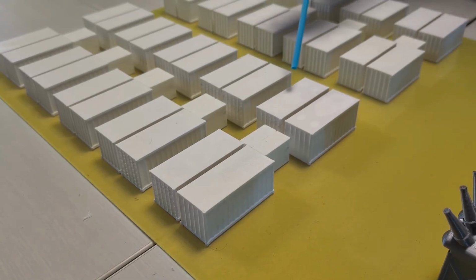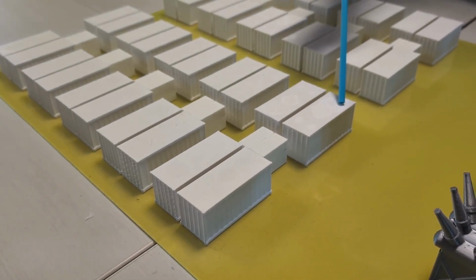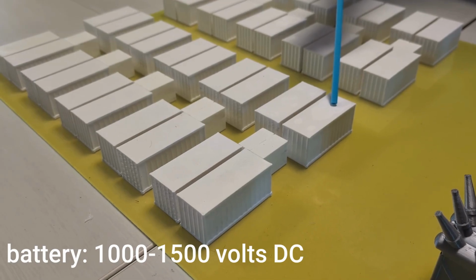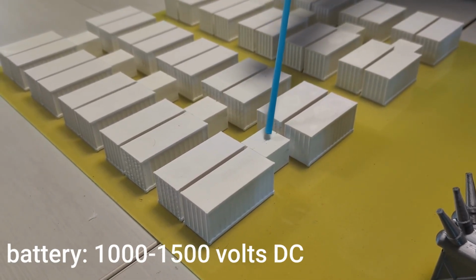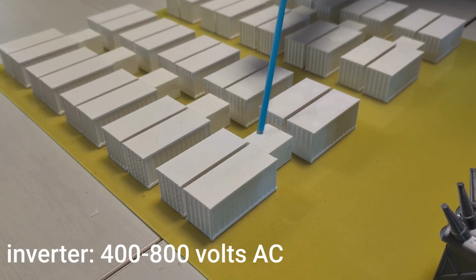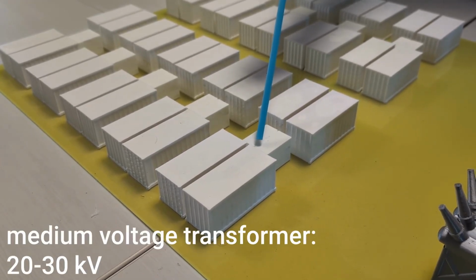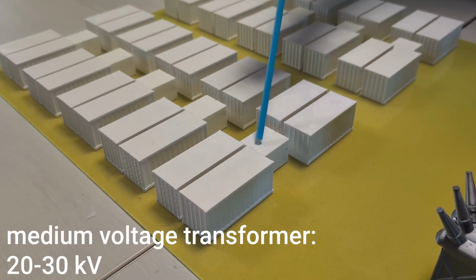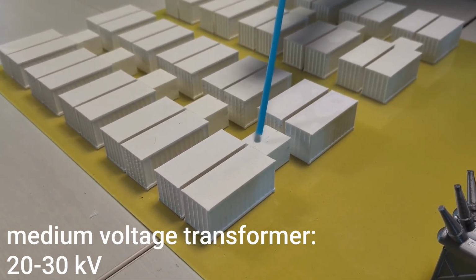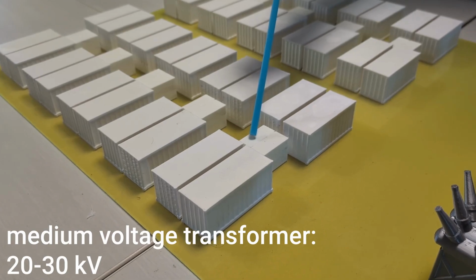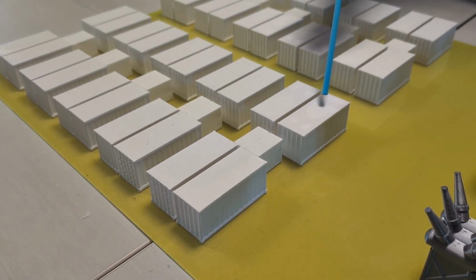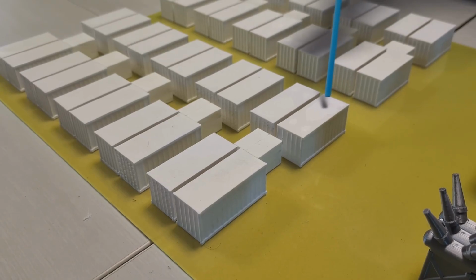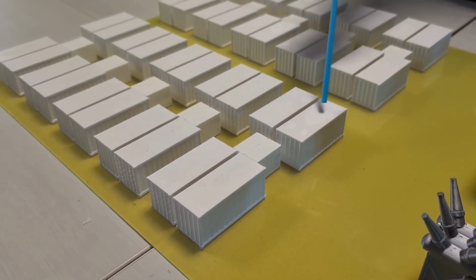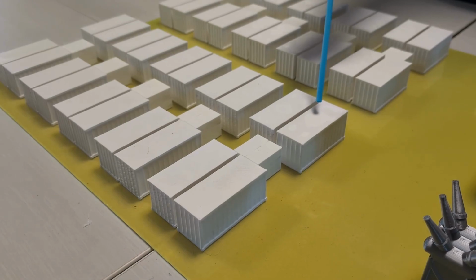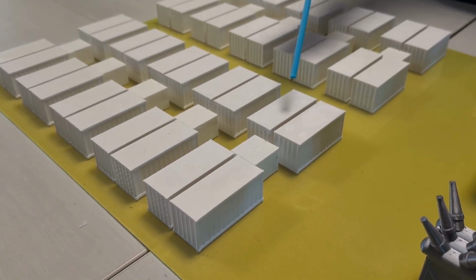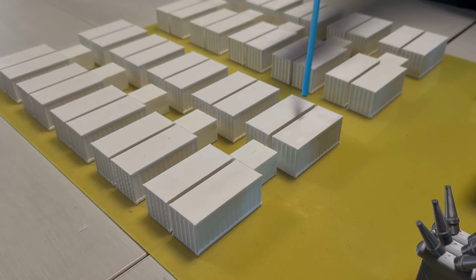Typical voltages for a system like this would be 1,000 to 1,500 volts DC on the battery side, somewhere between 400 and 800 volts AC coming out of the inverter, and usually somewhere between 20 and 30 kilovolts on the medium voltage transformer. The range on the DC side is because at 1,000 volts, that would be when the system is closest to 0% state of charge, fully discharged, up to close to 1,500 volts when it's fully charged.